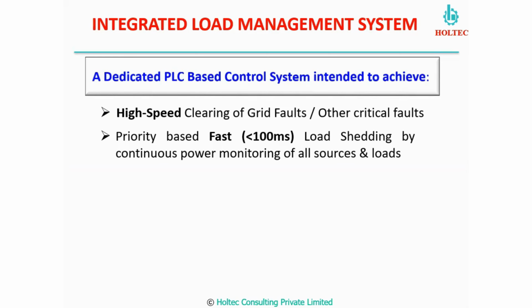This load shedding is done based on the required amount of load which we have to shed. Say we need to shed 5 megawatts, then it can select 5 megawatts of load and shed only that, or maybe 7 megawatts of unprioritized load, maybe 10 or 12 megawatts can be shed. In that way also we can prioritize and save production.